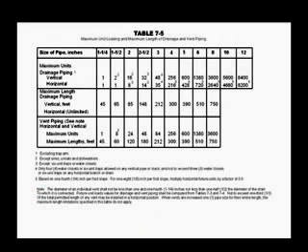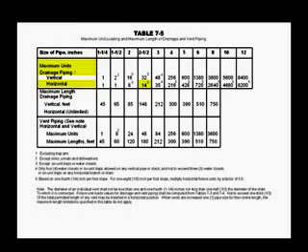Refer to table 7-5, Maximum Units Horizontal, and look for a size that can drain 10 fixture units. 14 fixture units will handle this, but notice the small number 3 besides the 14 for footnote number 3, which reads, except 6 unit traps or water closets. This exception tells us that the water closets cannot be drained through this size pipe. We must go over to the next column.